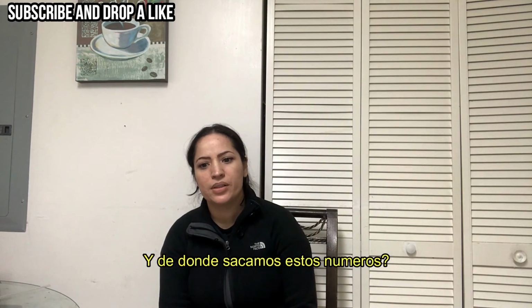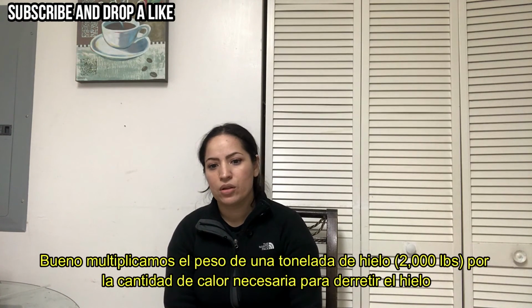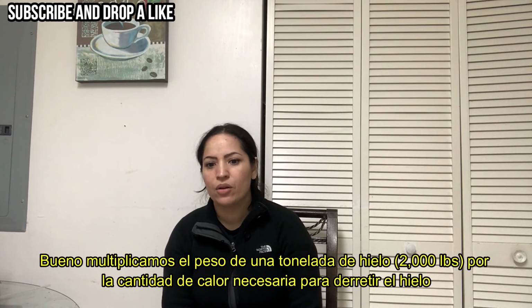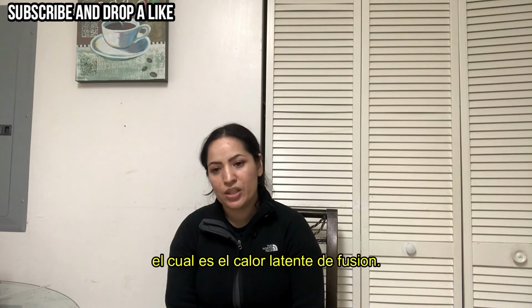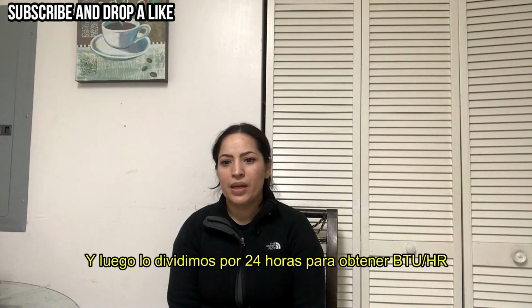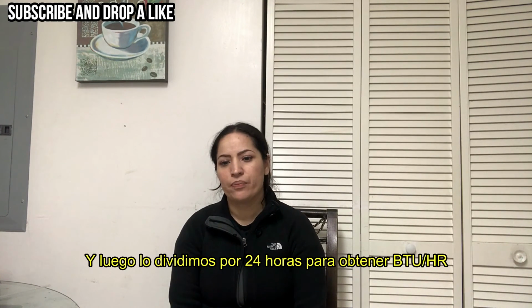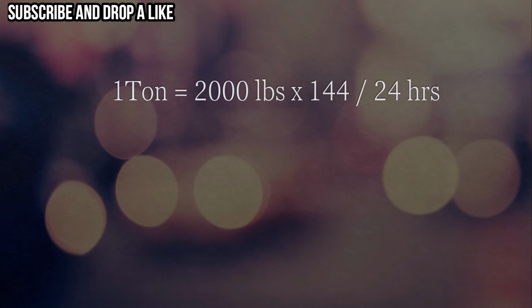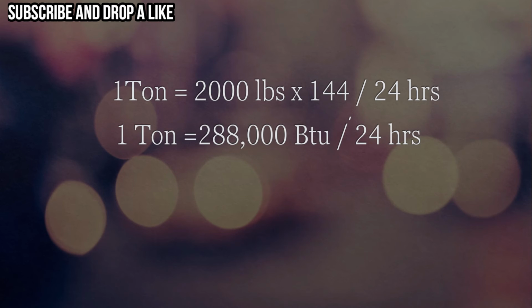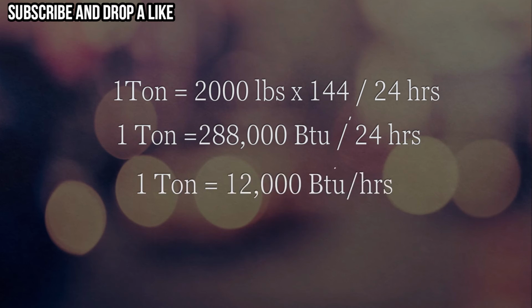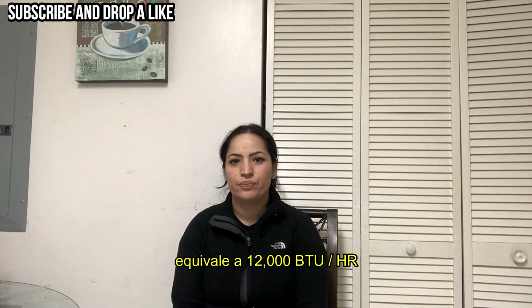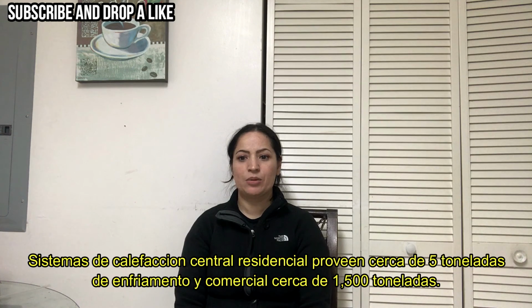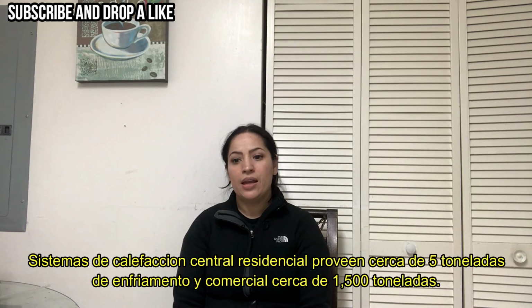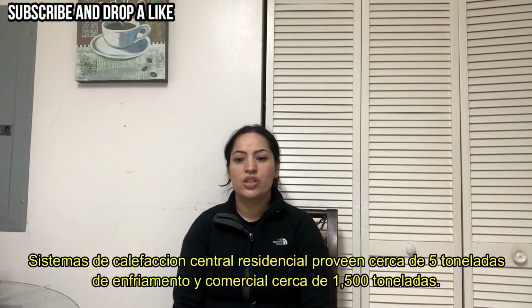So where do we get these numbers? Well, we multiply the weight of 1 ton of ice, 2,000 pounds, by the amount of heat required to melt the ice, which is the latent heat of fusion. Then we divide it by 24 hours to obtain BTU per hour. So that is 1 ton equals 2,000 pounds times 144 over a 24-hour period, which equals 288,000 BTU over 24 hours. That equals 12,000 BTU per hour. Residential central systems provide up to 5 tons of cooling, and commercial up to 1,500 ton chiller systems.